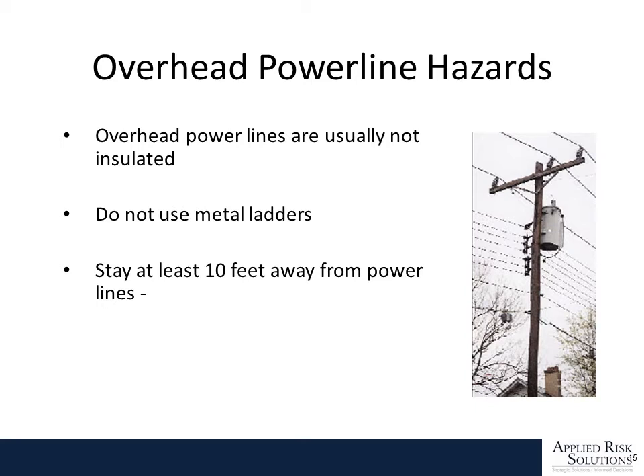Remember, electricity is trying to find its easiest path to ground. If you approach an overhead power line and become closer than 10 feet, it is possible for that power to jump from the line to you, and then you become part of the circuit to ground. And there are a lot of fatalities caused by people just approaching too close. It is an OSHA violation to get any closer than 10 feet from an overhead power line, and this includes anything that you're working on.